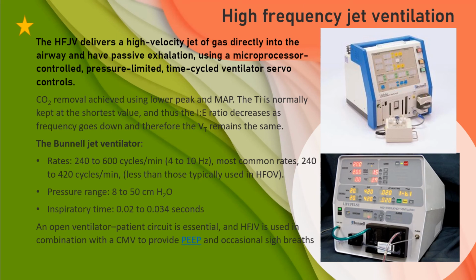High-frequency jet ventilation. The HFJV delivers a high-velocity jet of gas directly into the airway and has passive exhalation. It uses a microprocessor-controlled, pressure-limited, time-cycled ventilator with servo controls. CO2 removal is achieved using lower peak and MAP, and the I time is normally kept at the shortest value. Thus, the IE ratio decreases as frequency goes down, therefore the tidal volume remains the same.